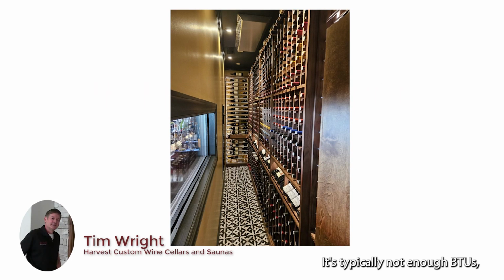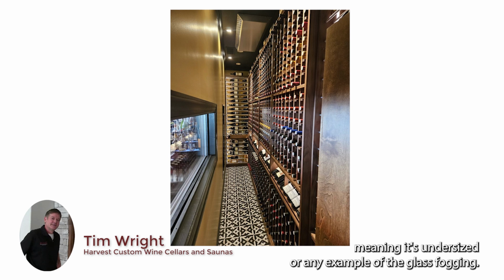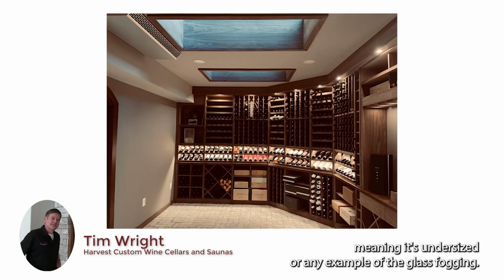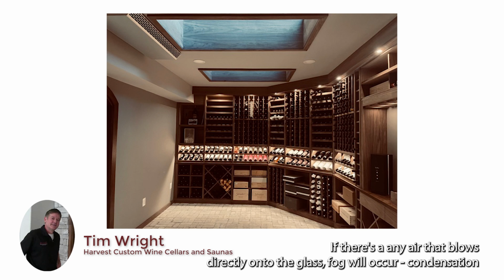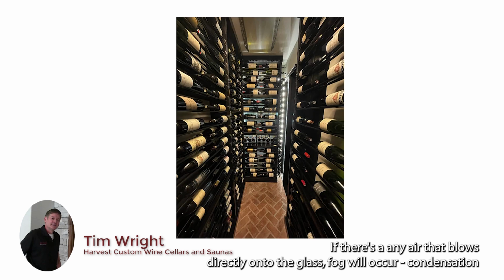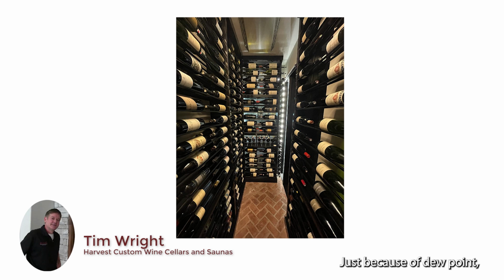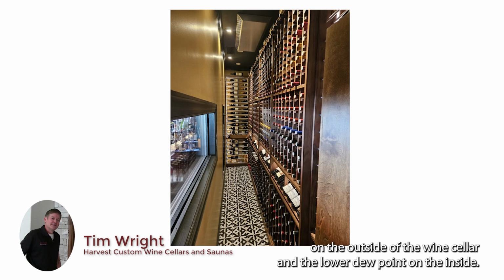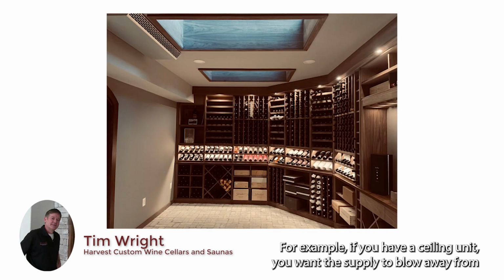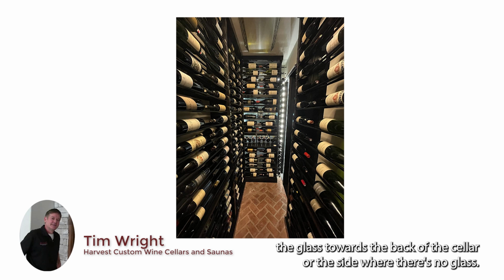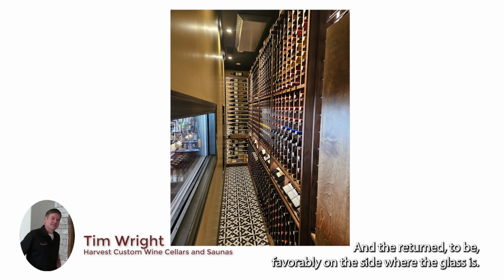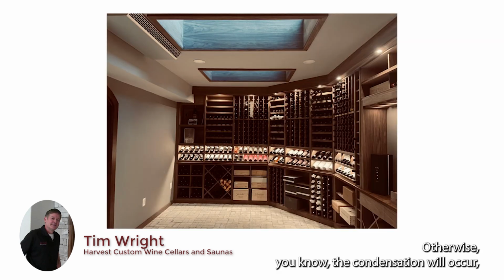It's typically not enough BTUs, meaning it's undersized. Or in the example of the glass fogging, if there's any air that blows directly onto the glass, fog will occur, condensation, just because of the dew point on the outside of the wine cellar and the lower dew point on the inside. For example, if you have a ceiling unit, you want the supply to blow away from the glass towards the back of the cellar or the side where there's no glass, and the return to be favorably on the side where the glass is. Otherwise, the condensation will occur.